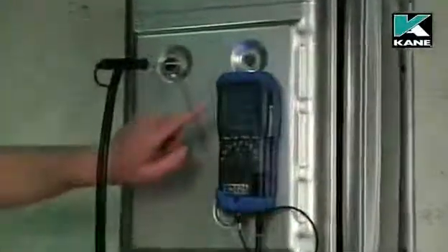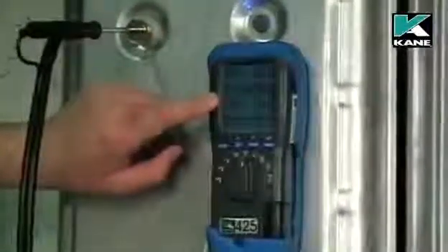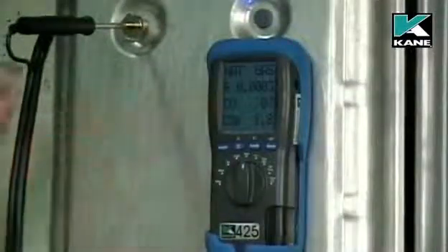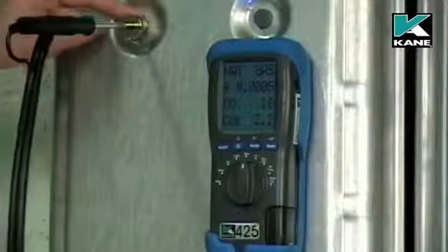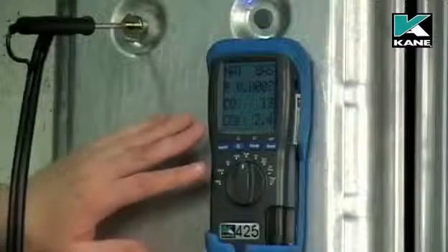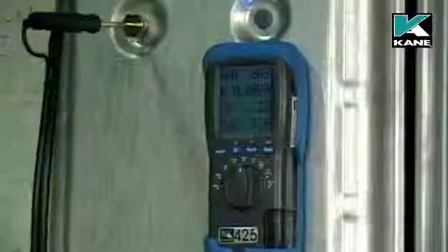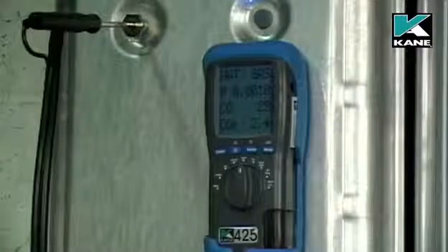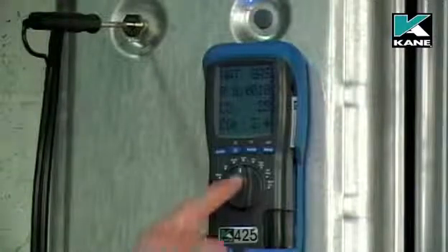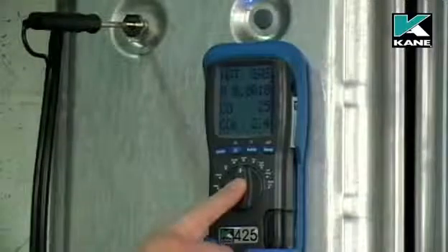Now you'll notice that the readings have about a 10-second delay. This is the time for the sample of flue gas to actually travel the length of the hose and be analysed. It is actually continuously sampling.